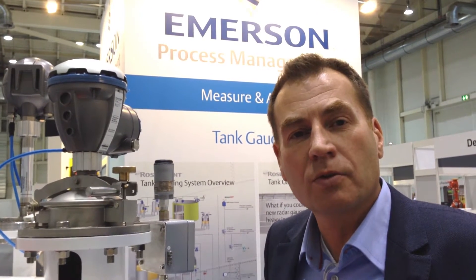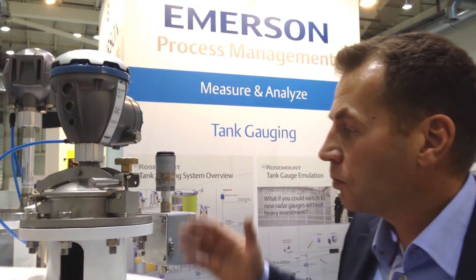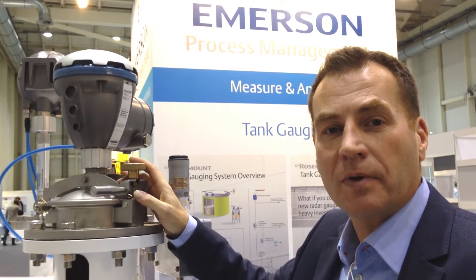You need to install automatic tank gauging and also be able to use that single steel pipe for verification and sampling. What we have here on this demo tank is a 5900S radar gauge with its steel pipe array antenna.